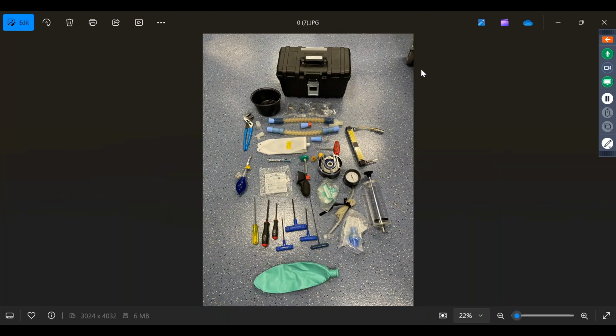What's in the crash kit? Diaphragm for the ventilator, test hoses, test lungs, a click adapter. Those things go bad pretty often. This is a flow meter for 1,000 cc's. So a lot of times the anesthesia machine, the Draeger Apollo, doesn't like it if there's any phantom flow through the oxygen valve when it's shut off. It messes up the calibration.